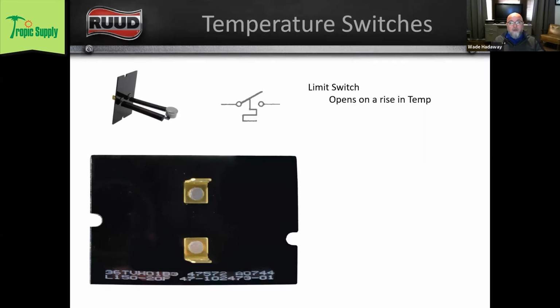I know most of you on this call probably don't have a lot of regular dealings with gas furnaces, but just like the pressure switch will show you what pressures the switch opens and closes at, the limit switch from a furnace does the same thing. You can see I drew a little red box around where it says L150-20F. And what that tells us is that this switch opens at 150 degrees Fahrenheit and closes at 130. So the L150 is the open temperature minus 20 degrees. So when we hit open and we cool down 20 degrees from 150, the switch will close again at 130 degrees. That's what that means.